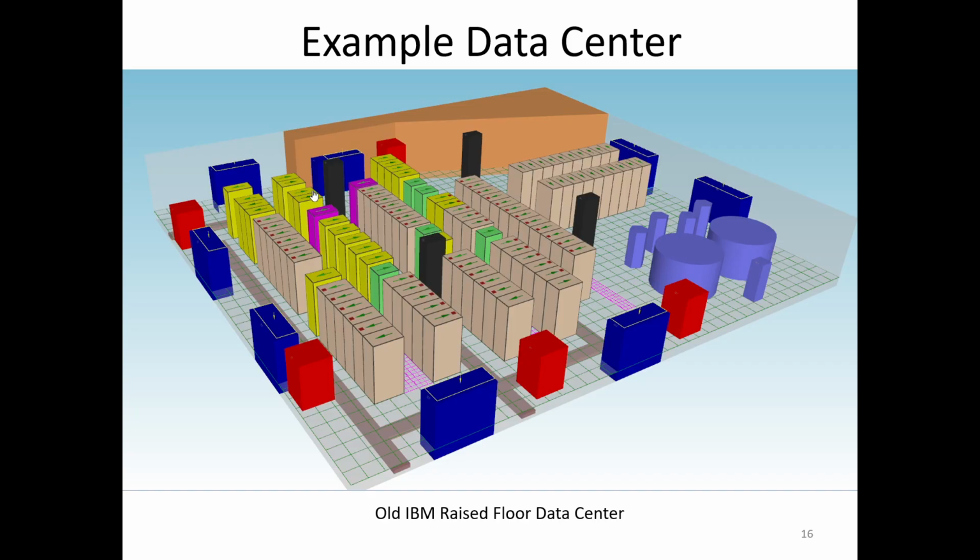The racks are lined up correctly. Hot aisle, cold aisle, that's not so much of a problem. You see the airflow indicator suggests that this is the cold aisle, and this is the hot aisle over here, and so it alternates as it goes across.